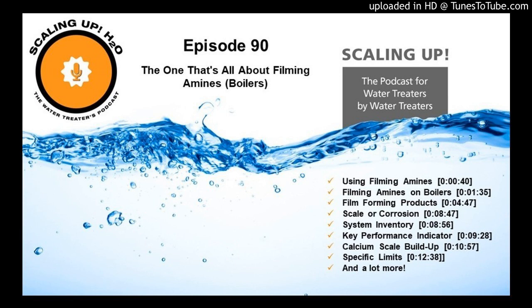So my answer is actually kind of twofold. My first response is, okay, so you can measure all of those things. In a conventional program, you can measure polymer, you can measure sulfite, pick them all, you can measure them all. But what's your ultimate marker for success? You open that boiler up and it looks good. Or you pay attention to your iron levels. It's corrosion rate. That's ultimately our marker for are we doing well, is what's the corrosion rate in that system. Or if you open it up, does it look good? Is it clean? Right?